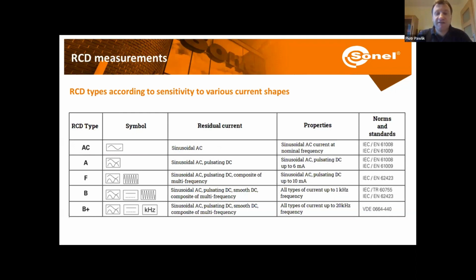Now, why is that? Well, we have plenty of different computers and electronic devices. For example, even my laptop or my monitor over here are powered by DC current, so we can expect that rectifiers are connected. Rectifiers will cause some harmonics in our network. So that's why the fault currents will not have a nice sine wave. They will have some sort of distorted signals.